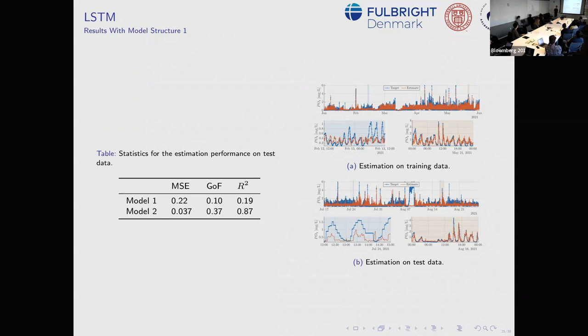We have more than a year of data, so all training is done with more than one year. We tried to test on the same kind of season but not the same data, since we have multiple years. Even within the same season, it's not proportional because Denmark's weather is completely unpredictable, and the microbiology changes — the disturbance from municipalities can change, industry can let out chemicals with unfavorable pH, and so on.